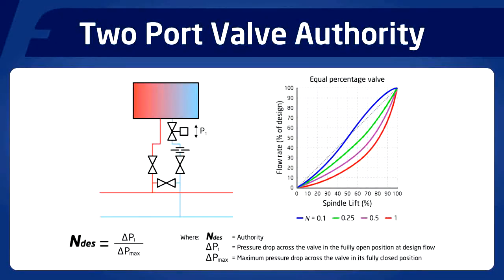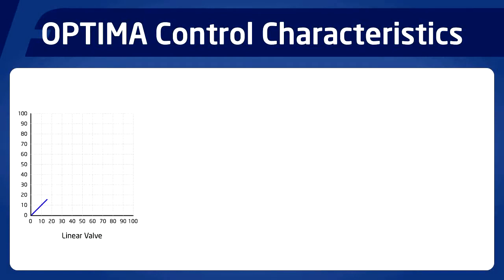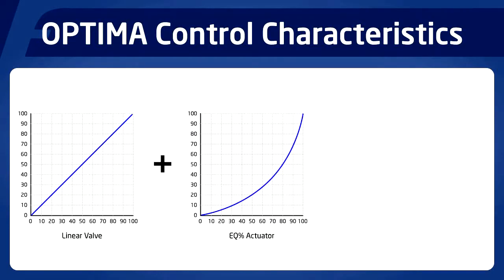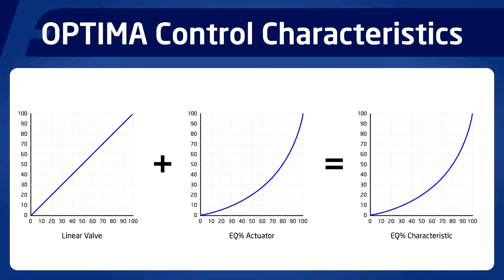If we allow the authority to drop, then this reduces the resistance, but unfortunately the equal percentage control characteristic that we aim for is now no longer achievable. The OPTIMA valve is actually linear, but when we install the actuator that is pre-programmed with an equal percentage characteristic, the combined characteristic of the control valve is equal percent.